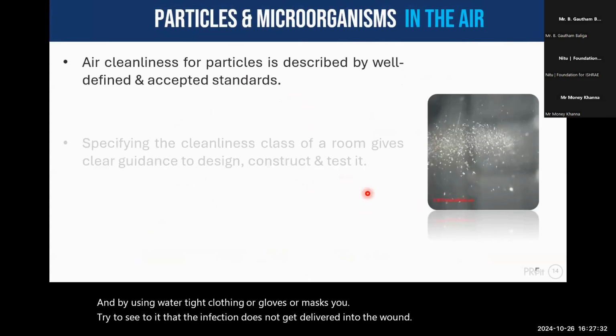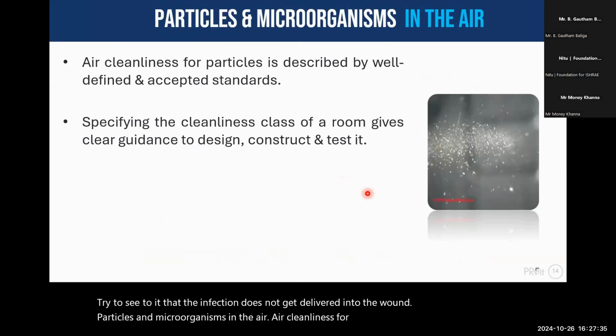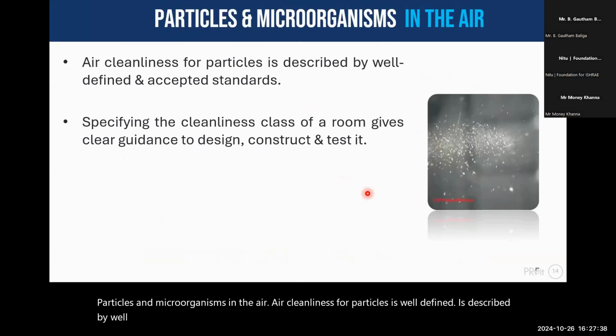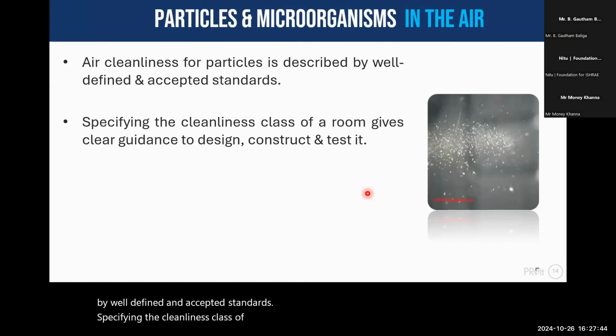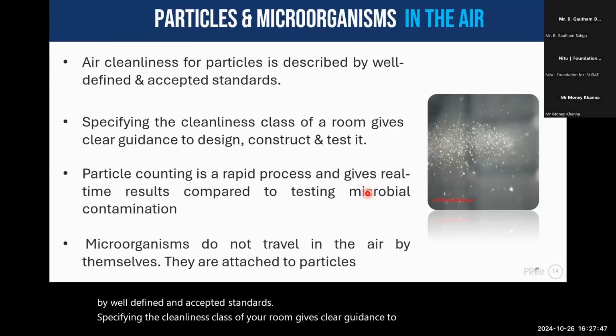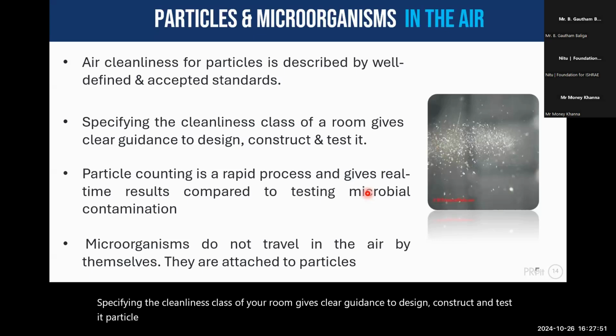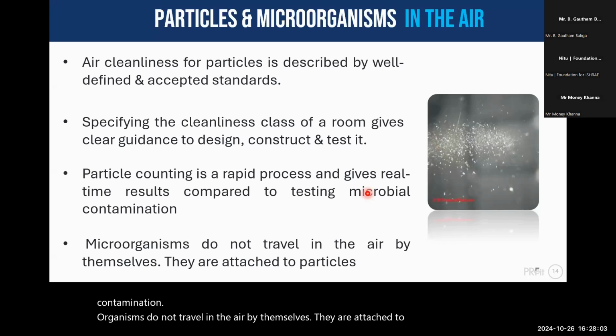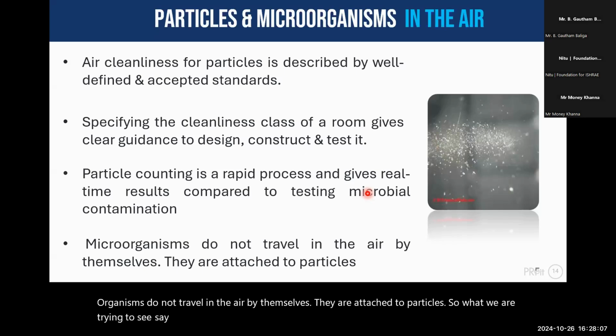Particles and microorganisms in the air. Air cleanliness for particles is described by well defined and accepted standards. Specifying the cleanliness class of a room gives clear guidance to design, construct, and test it. Particle counting is a rapid process and gives real time results compared to testing microbial contamination. Microorganisms do not travel in the air by themselves, they are attached to particles. So what we are trying to say in this slide is that we look at particles, how to control the particles, and as a result of that, we control the microorganisms.